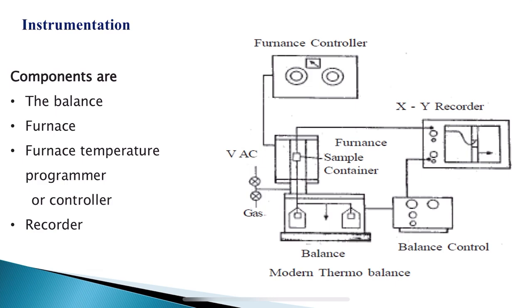The temperature is measured by a thermocouple or resistance sensor. Okay. We use the resistance sensor to measure how much temperature the furnace contains, and the heating is controlled by a computer system. The whole instrument will be connected to a computer, and the temperature control will be adjusted with the help of the computer.